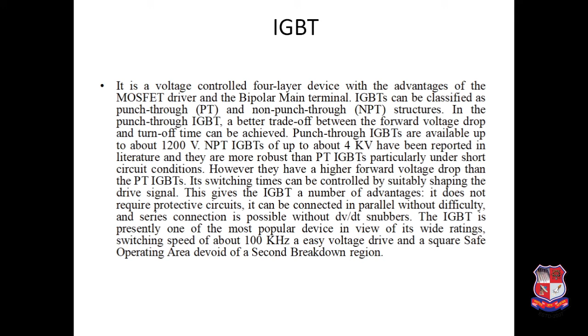Then the IGBT has a number of advantages: it does not require a protective circuit, it can be connected in parallel without any difficulty, and a series connection is possible without any snubber circuit for dV by dt. The IGBT is the most popular device in view of its wide rating and switching of around 100 kilohertz. So for the wide range of frequency available here, the most frequently used device is the IGBT.